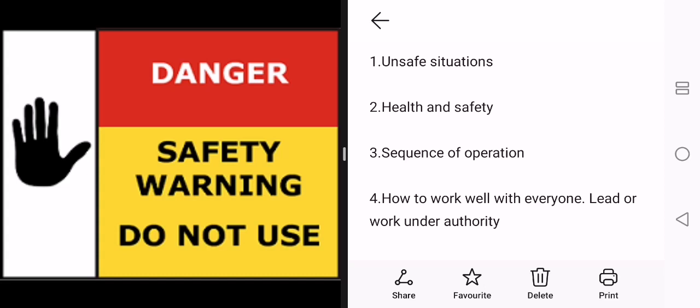You need to know whether you can leave the boiler running and get the signature from the client because of what it's categorized as and how dangerous the situation is. You don't have to be a robot. You have to also understand why these laws are in place and why you are shutting off the gas supply and so on. It's a legal matter. So know this. It's important to know your unsafe situations. I think you should try to know them by heart and know what to do accordingly in a dangerous situation, and what paperwork to fill out, what warning notice to put on, how to shut off the appliance, and etc.